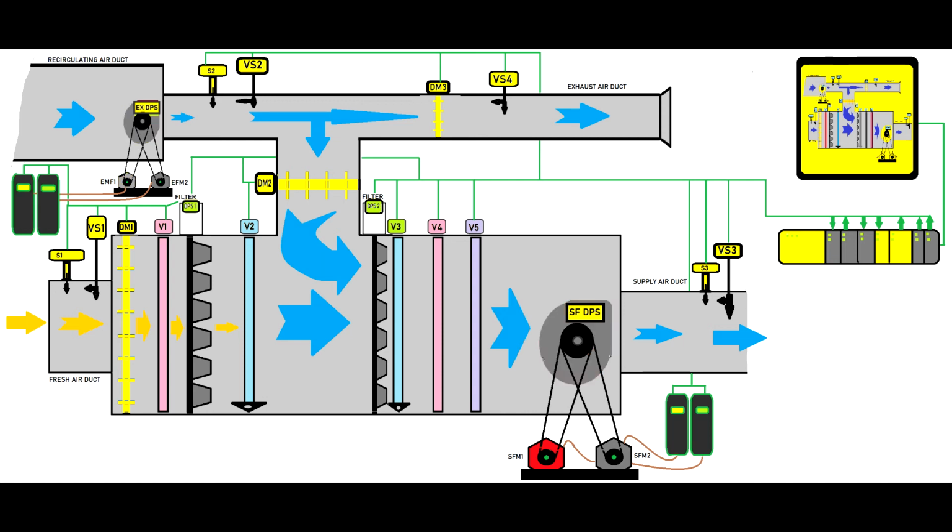And then 3 minutes later, in my case, it will re-enable the fans, but then we'll swap the motors. They will try to use the motors which have less running hours. But even if the motor starts on the standby motor, on the HMI you can see you have an alarm that tells you one of the motors is broken.